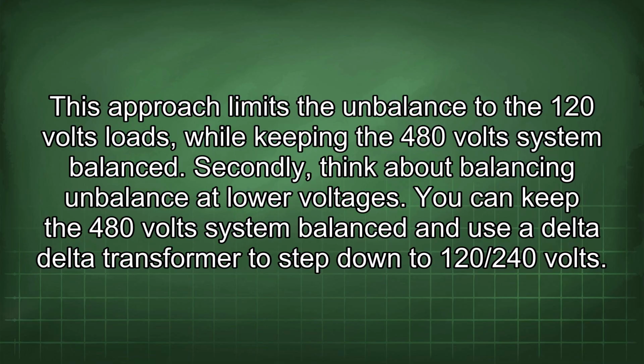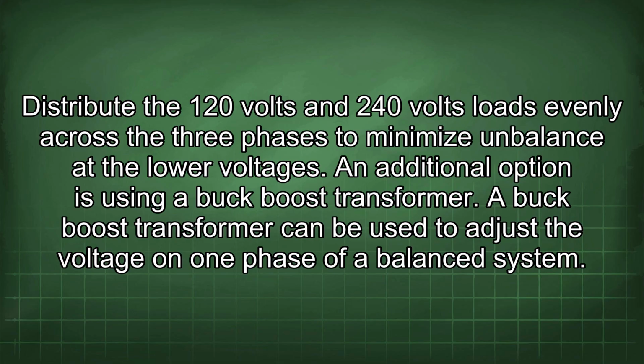Secondly, think about balancing imbalance at lower voltages. You can keep the 480 volt system balanced and use a delta-delta transformer to step down to 120/240 volts. Distribute the 120 volt and 240 volt loads evenly across the three phases to minimize imbalance at the lower voltages. An additional option is using a buck-boost transformer.